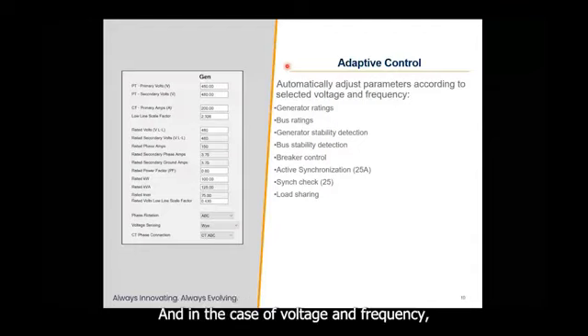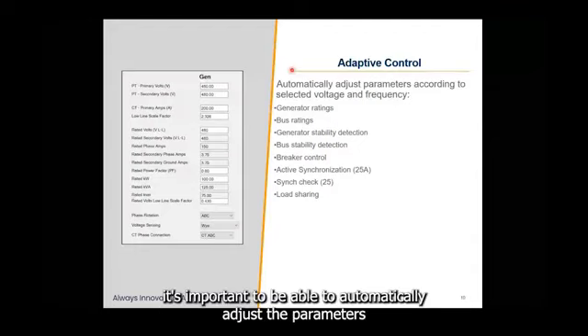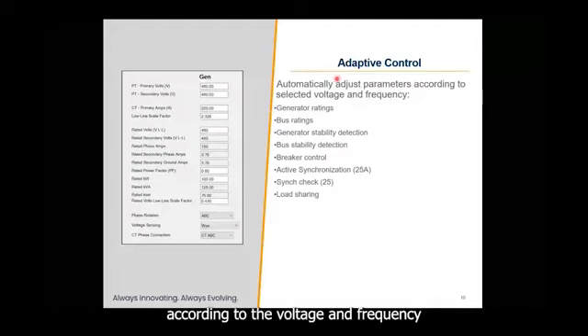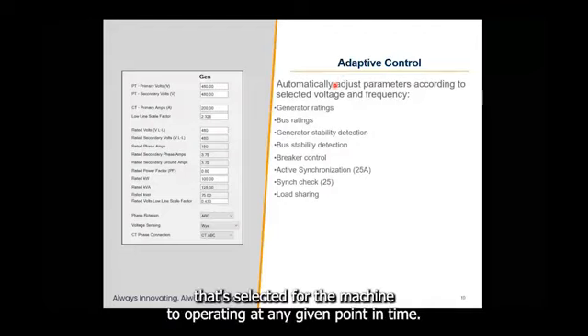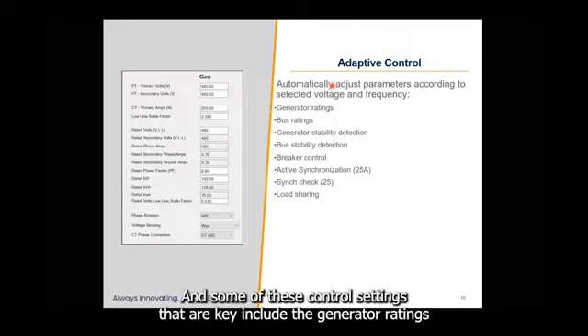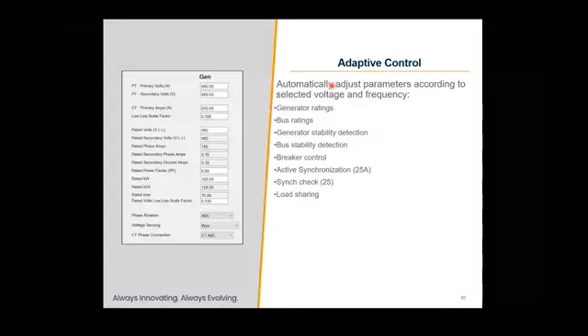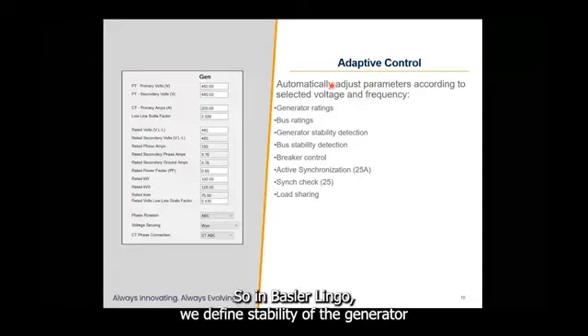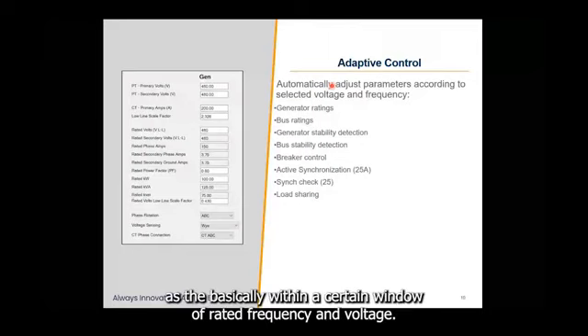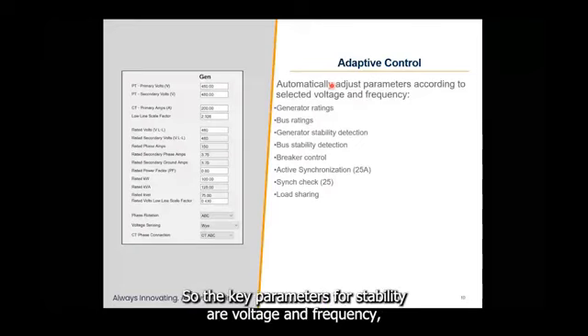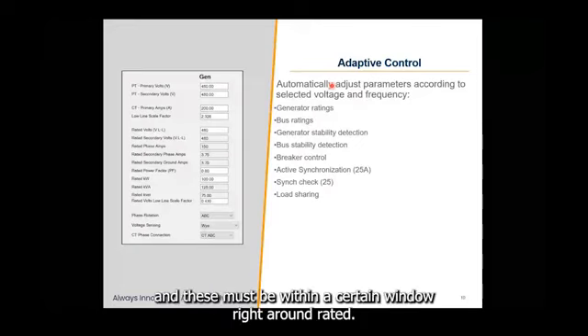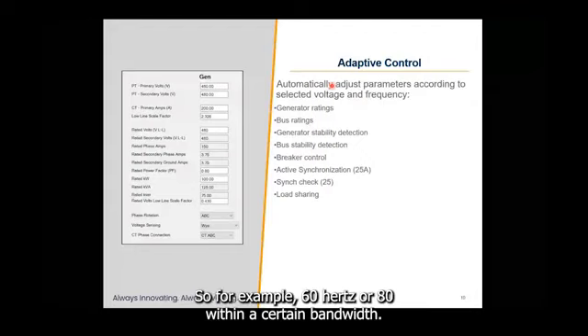And in the case of voltage and frequency, it's important to be able to automatically adjust the parameters according to the voltage and frequency that's selected for the machine to operate in at any given point in time. And some of these control settings that are key include the generator ratings, as well as the bus ratings, generator stability detection. So in Basler lingo, we define stability of the generator as basically within a certain window of rated frequency and voltage. So the key parameters for stability are voltage and frequency, and these must be within a certain window right around rated. So for example, 60 hertz, 480 within a certain bandwidth.